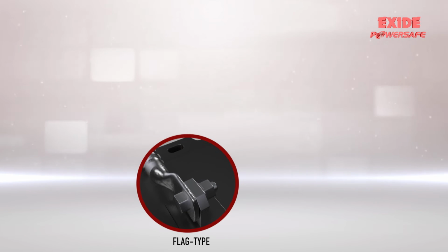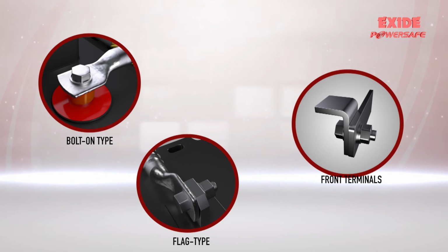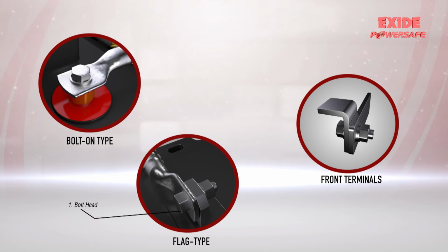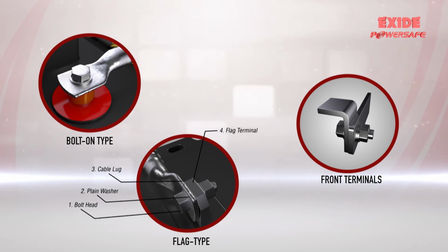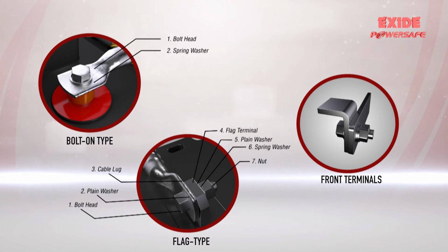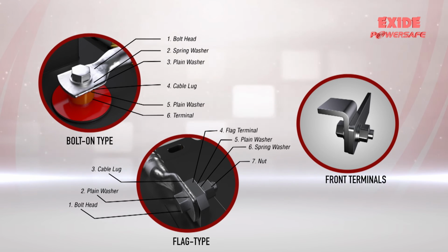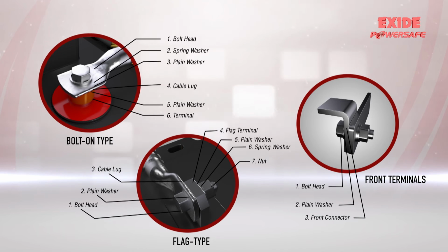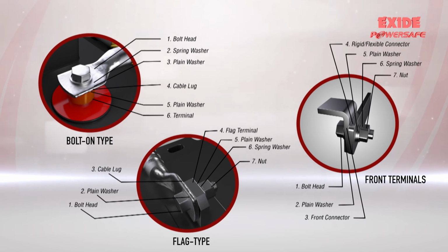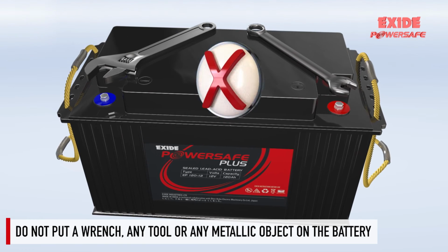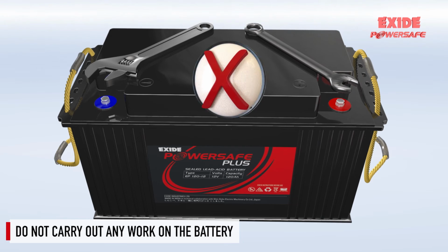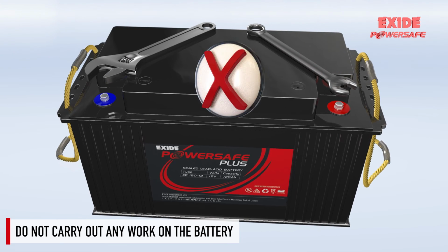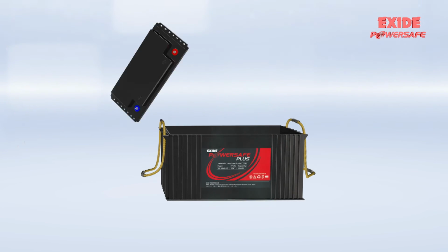Fasteners arrangement for flag type, bolt-on type and front terminals should be as shown. Bolt, plain washer, cable lug, terminal, plain washer, spring washer, nut. Bolt head, spring washer, plain washer, cable lug, plain washer, terminal. Bolt head, plain washer, front connector, rigid connector or cable lug, plain washer, spring washer, nut. Do not put wrench, tool or metallic object on the VRLA battery, nor carry out any work on the VRLA battery. It can cause short circuit and damage the battery.